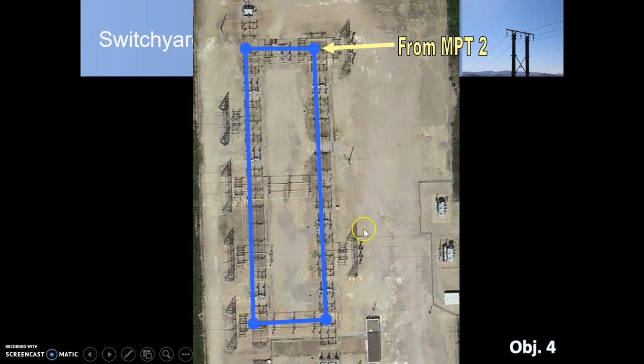Another feature that you'll see in this particular photograph is a direct feed from 345 kV bus 3 to transformer 86. Transformer 86, if you remember back, is the main feed or the normal feed to transformer 22.